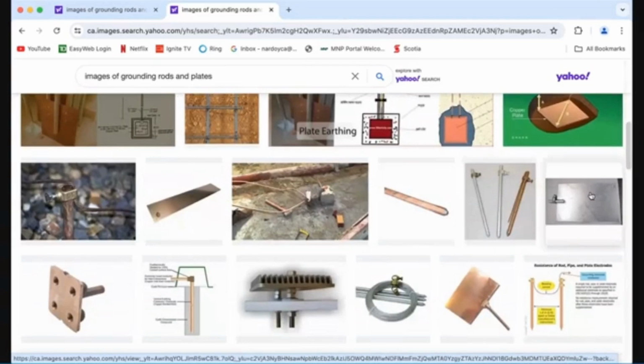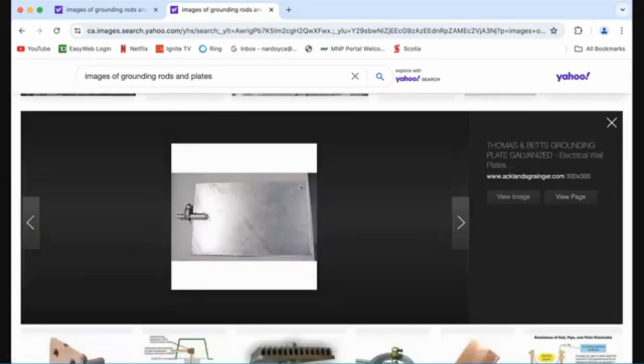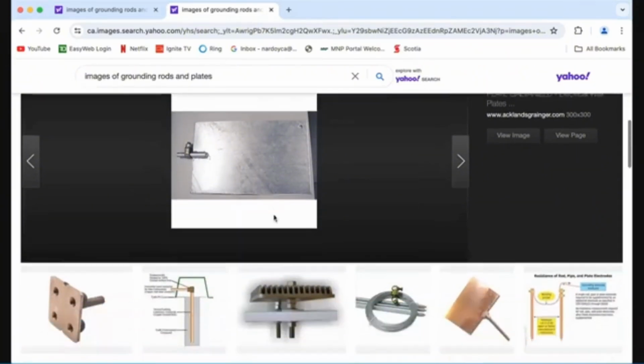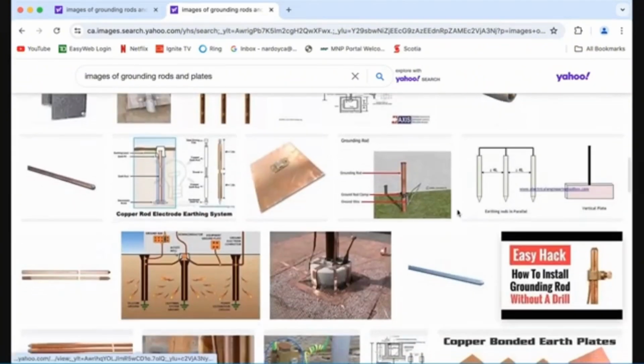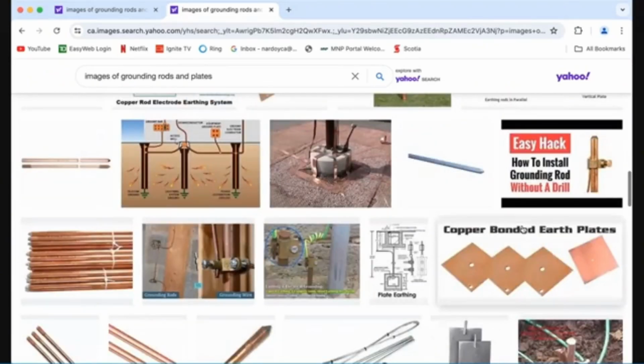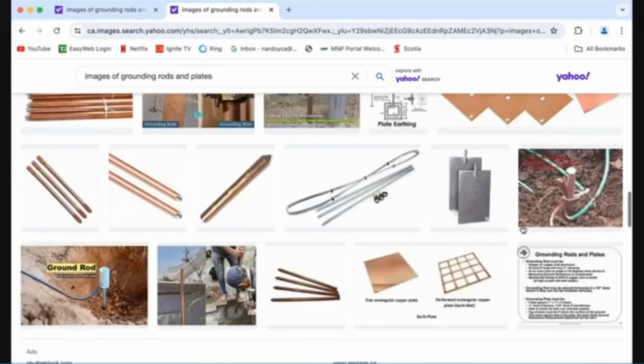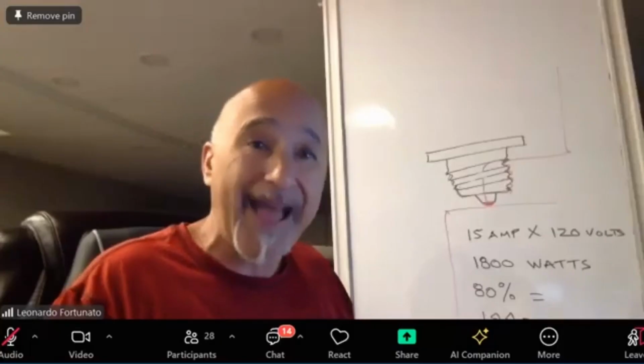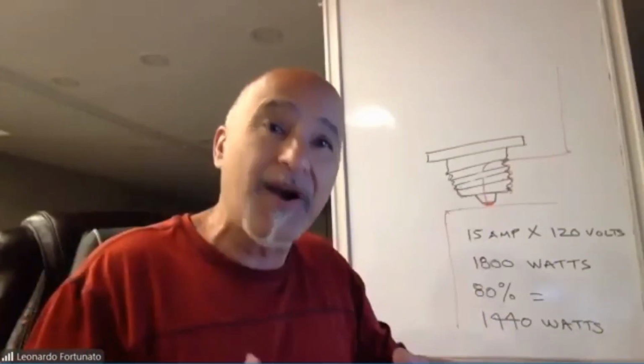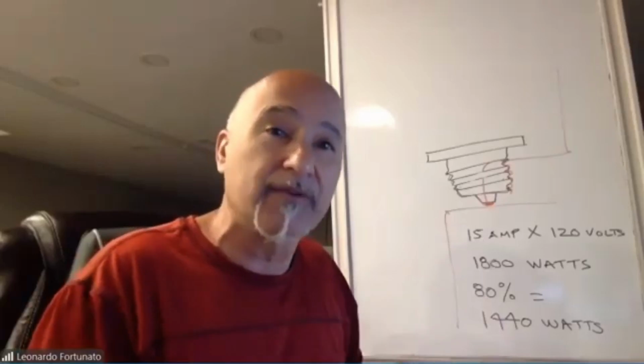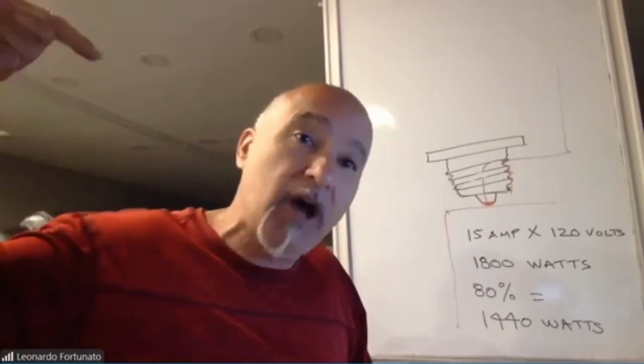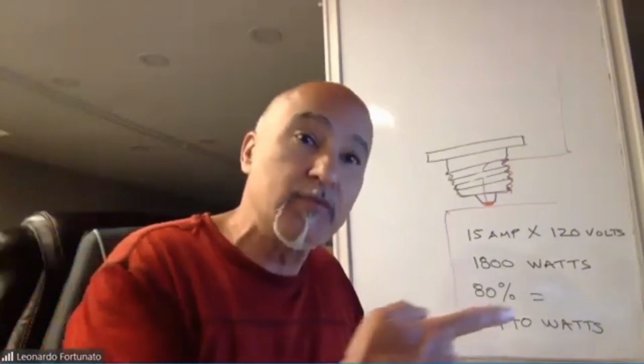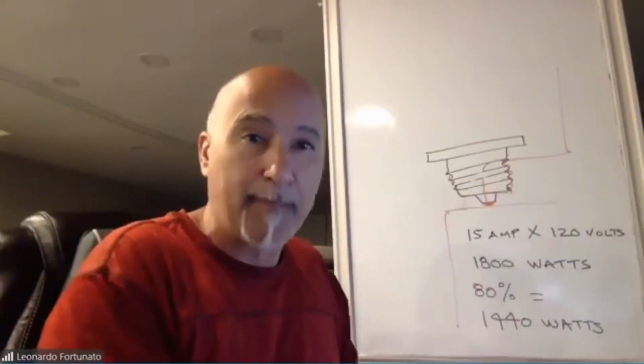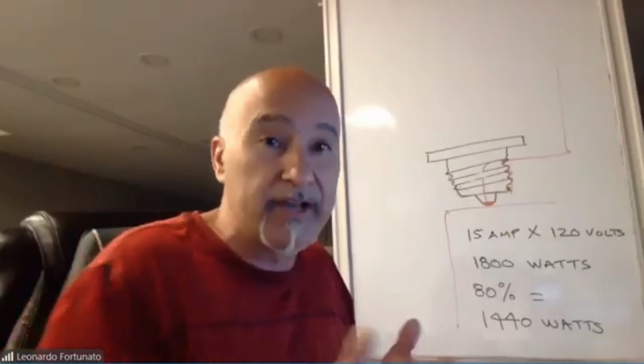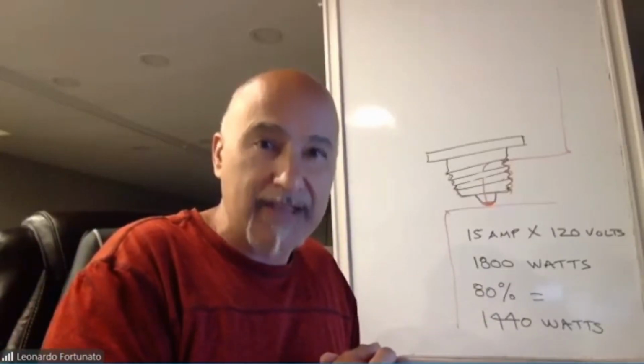This is a grounding plate. We would connect the wire to this plate, and we would make sure it's deep in the ground, at least 6 to 8 feet. And we would use a grounding rod or a grounding plate if the water supply is not copper. That copper pipe is deep in the ground, at least 6 feet. And because it's copper, it allows the copper wire to continue making that power flow through the copper pipe, so it continues the wire into the ground. Clarification there? Does that make more sense?